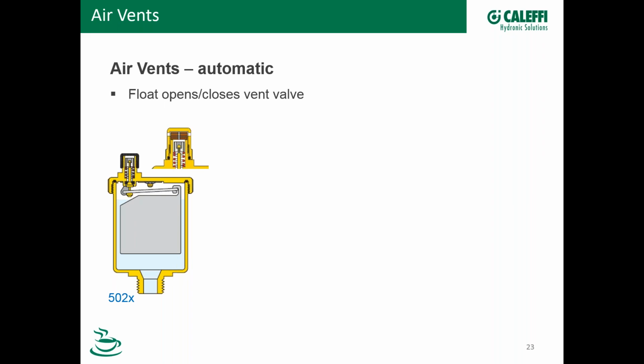Here's a cap. Now, the air vents that we sell are available with the hygroscopic cap that I just talked about. So those are options. If you get an air vent that just has a plastic cap like this, you can put a hygroscopic cap on there if you want to. And then down below, we have something called a service check valve. Now, we offer models that have this, or you can buy it separately. And what that device is, it screws on the bottom of the air vent, and it allows you to remove the air vent if you have to service it for some reason, and that little spring-loaded stop on the bottom closes, so you don't have to open a valve in the system or anything. It's like a Schrader valve type of spring-loaded valve that will close if you need to remove the vent.